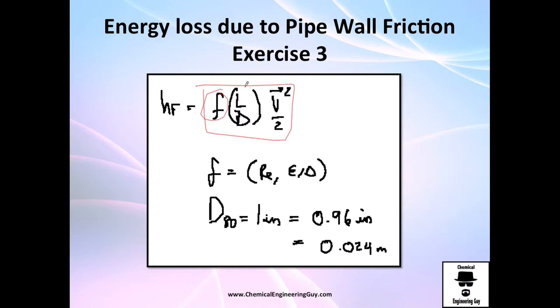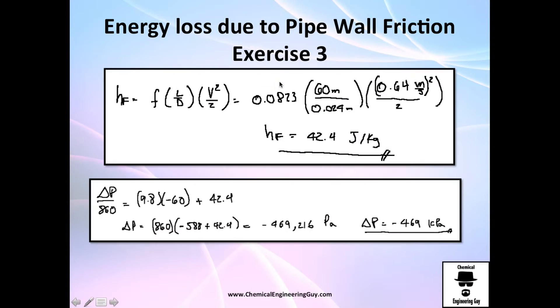But don't forget that we must calculate the energy loss, not the friction factor per se. So we got this right here. Let us substitute everything. We got this, we got the length which is 60 meters, the diameter which is 0.024 meters, and the velocity squared divided by 2. You get this number right here: 42.4 joules per kilogram. And I just want to let you compare it with exercise number two, the previous video. In the previous video we got something very very small, something about 0.03 joules per kilogram which is literally nothing. And in this case because we have a very high pressure drop, we have it right here, it's very high.